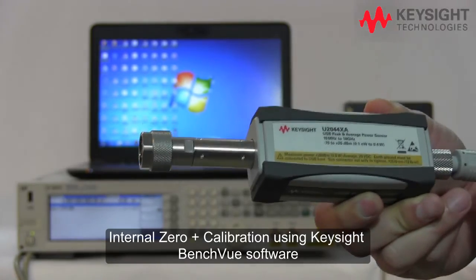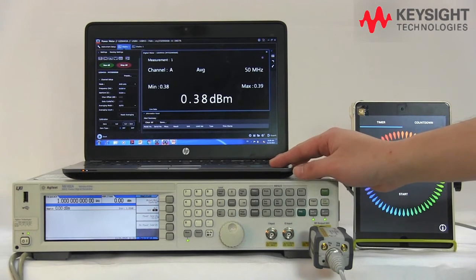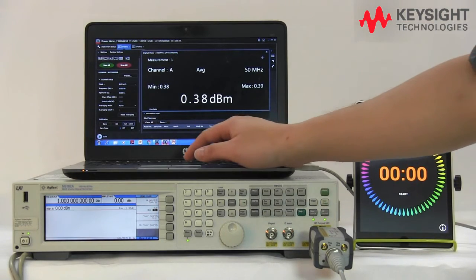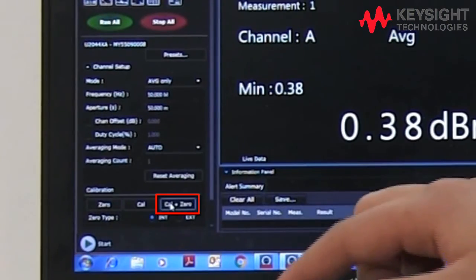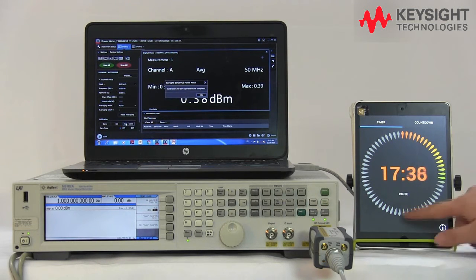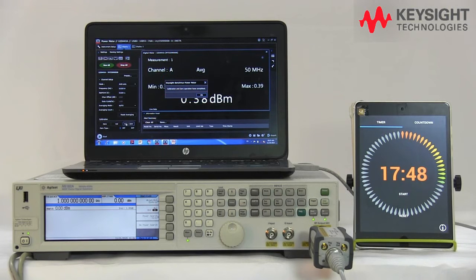Let's take a look at how we can perform the internal zero and cal using our Keysight BenchVue software. Here we have a USB power sensor connected to our PC running BenchVue, and the sensor is connected to a signal generator as the signal source. Let's run the cal and zero on the USB power sensor. Let's start the clock — this will normally take a couple of seconds. When it's completed, a pop-up message will appear. As you can see, the message has popped up and it only took about 17 seconds — way faster compared to the conventional method.